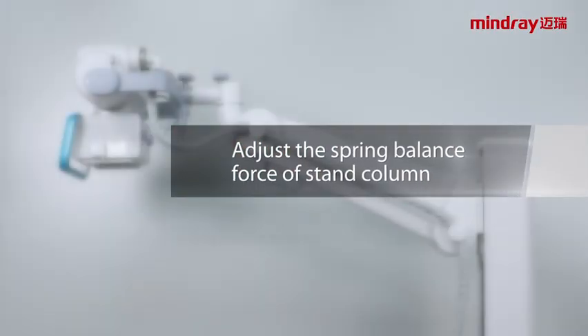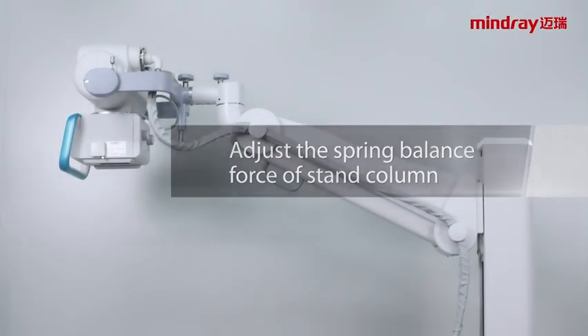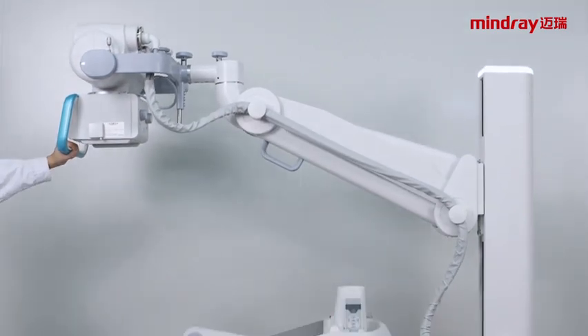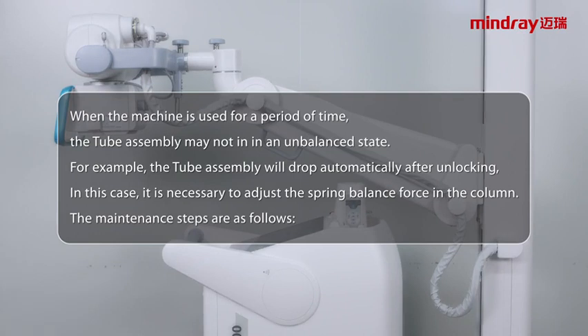Adjust the spring balance force of the stand column. When the machine is used for a period of time, the tube assembly may be in an unbalanced state. For example, the tube assembly will drop automatically after unlocking. In this case, it is necessary to adjust the spring balance force in the column. The maintenance steps are as follows.